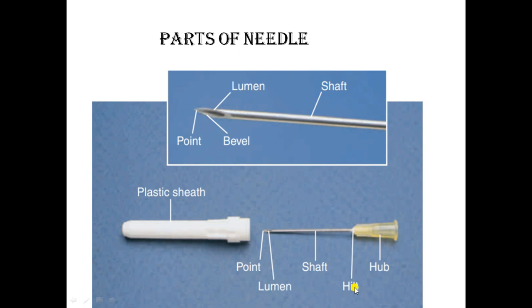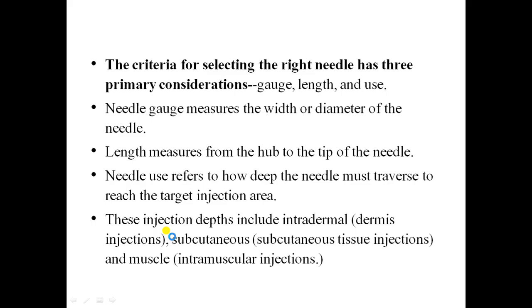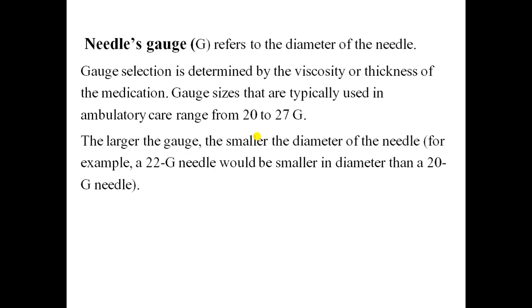The criteria for selecting the right needle involves three primary considerations: gauge, length, and use. Needle gauge measures the width or diameter of the needle. Length is measured from the hub to the tip. Needle use refers to how deep the needle must travel to reach the target injection area — intradermal, subcutaneous, or intramuscular.